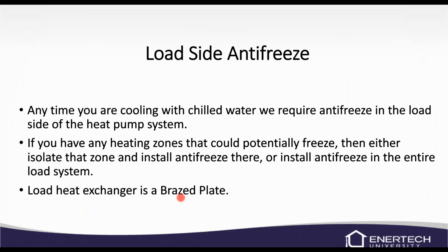Load side antifreeze, we know we're going to need it on the source side. So anytime you're cooling, we're using chilled water, we require antifreeze in the load side of the heat pump. If you don't put antifreeze in it, that water could freeze and it's going to burst that braze plate. So if you have any heating zones that could potentially freeze, in a garage, let's say, you're doing radiant in the garage, or you're doing some floor melt or ice melt, then you're going to have antifreeze in those locations. So either isolate those zones and install antifreeze there, or just put antifreeze in the entire load system.